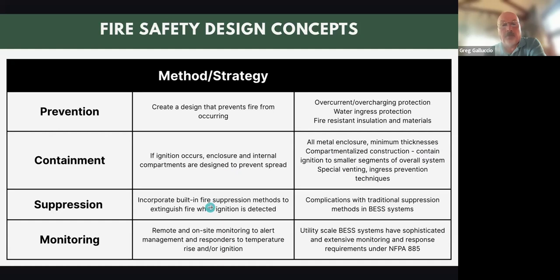The third is suppression—an automatic fire-extinguishing method, like a halon system or a water sprinkler system as you'd see in buildings. This is a problem for BESS systems: you can put out a lithium fire with water, but if you spray water on one contained, burning container within a larger BESS system, you may ignite the other compartments. So automatic fire suppression is not recommended at this time.